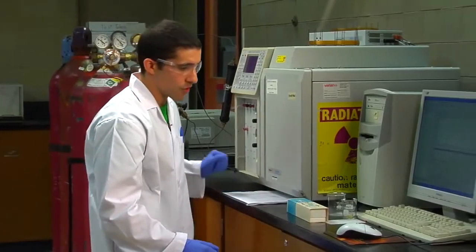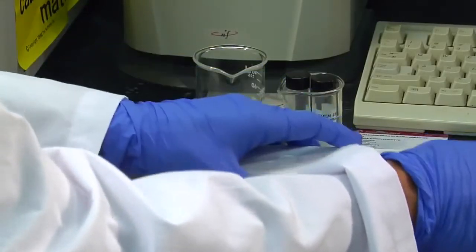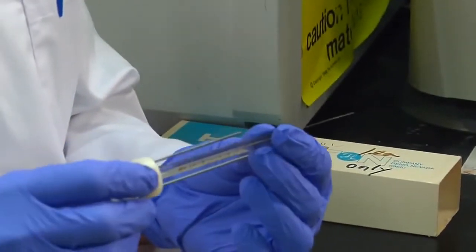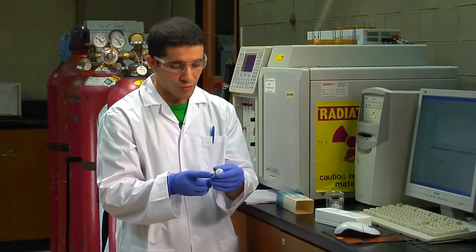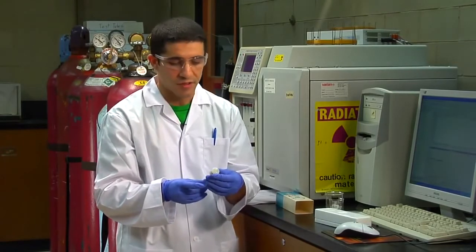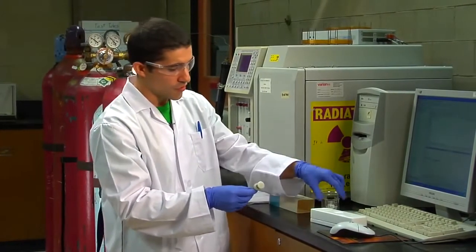So at this point, you can now prepare to do your injection. You'll be using a micro syringe. It'll look just like this. It's a 10 microliter micro syringe. And you'll need to clean the syringe prior to use to remove any contaminants that might be present from a previous experiment that was performed.